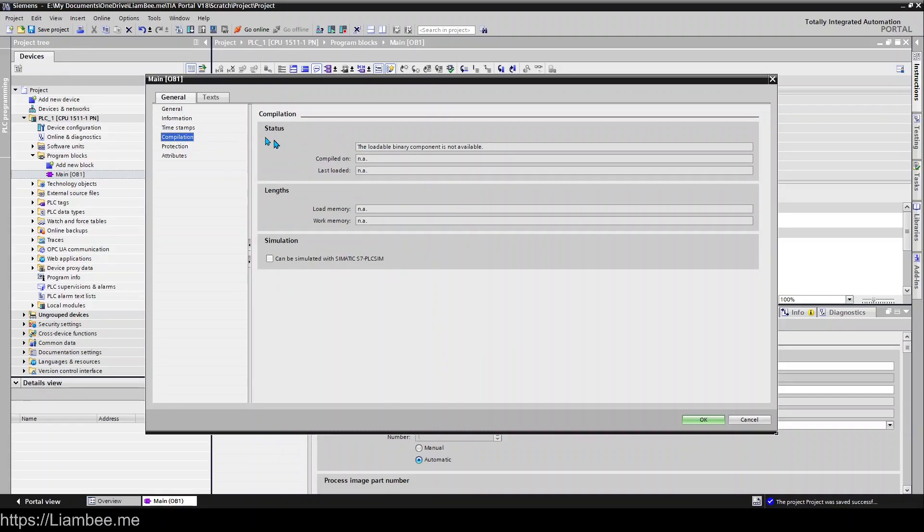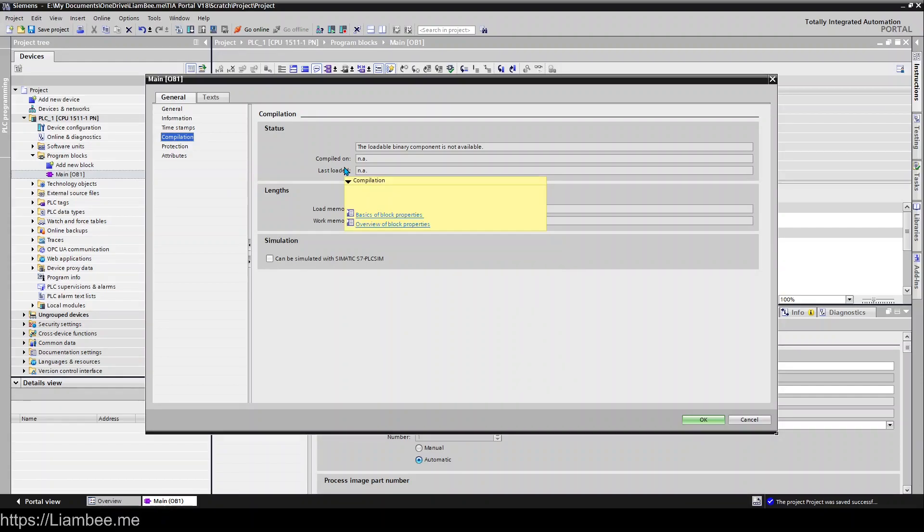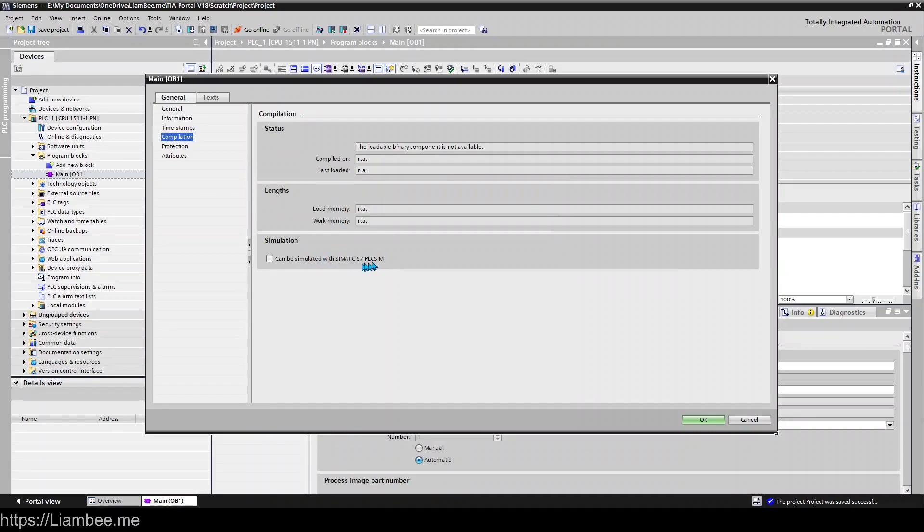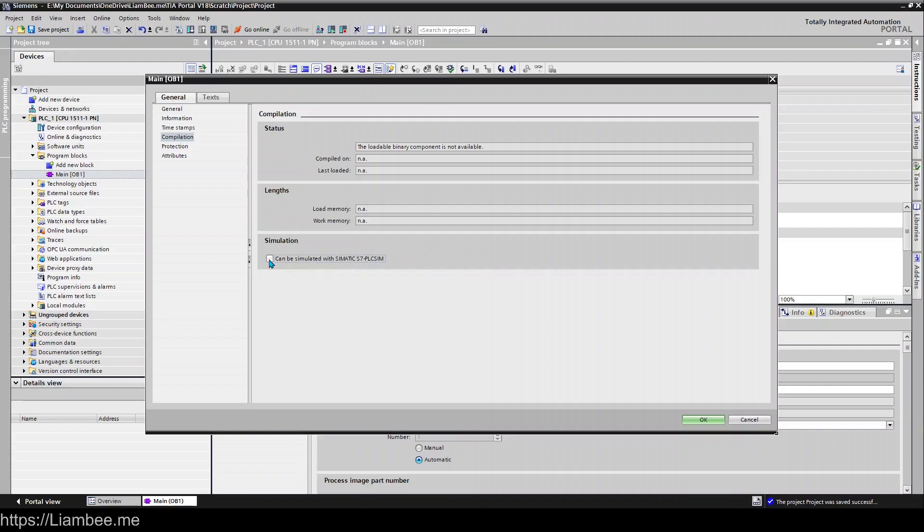So Compilation. This is one that will catch people out at the beginning. TIA Portal does not automatically turn on Can Be Simulated with PLC Sim and you'll also find that you can't turn it on here either. And that's because this block belongs to the project and the project has a configuration for simulation which I'll show you after, that will need to be turned on if you want to simulate your blocks.